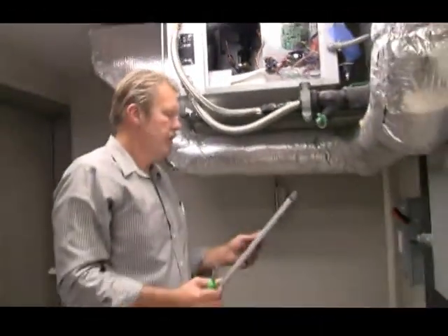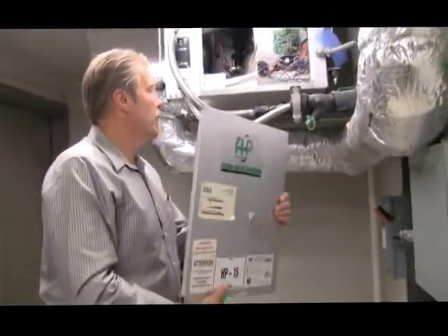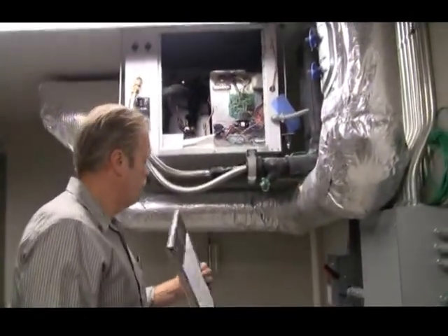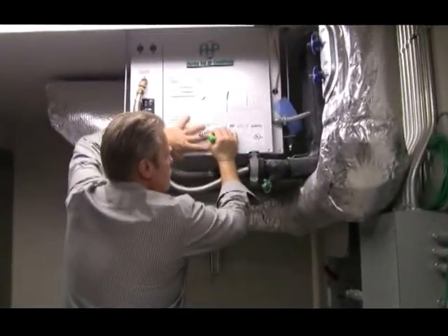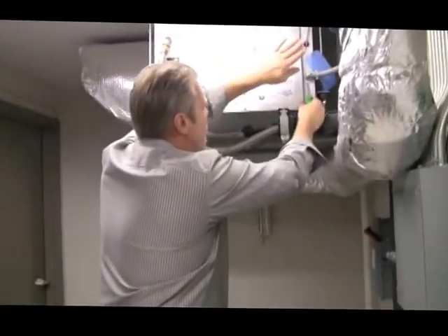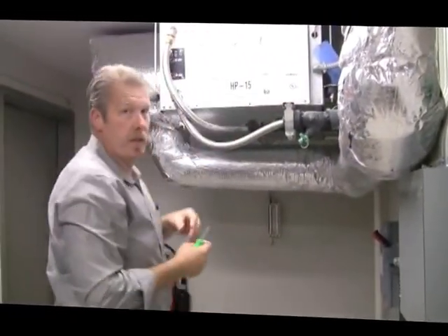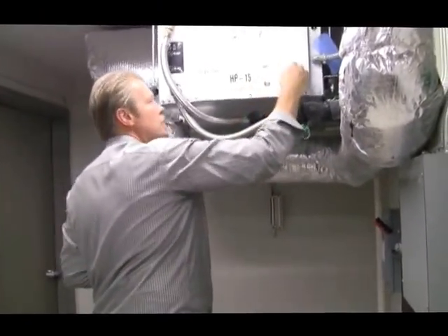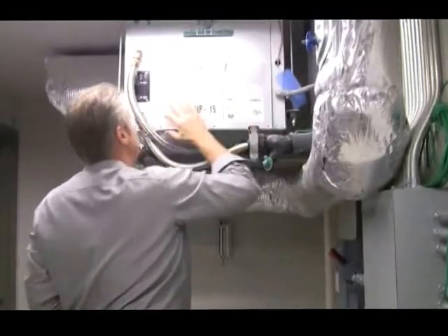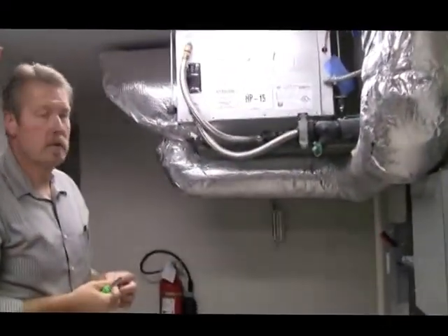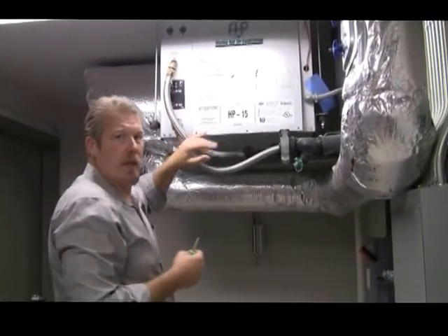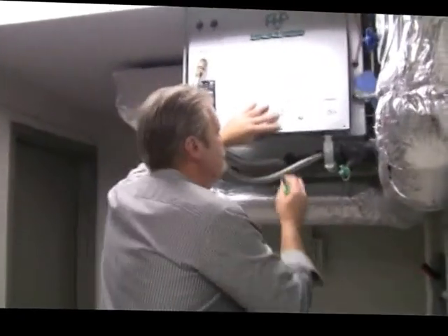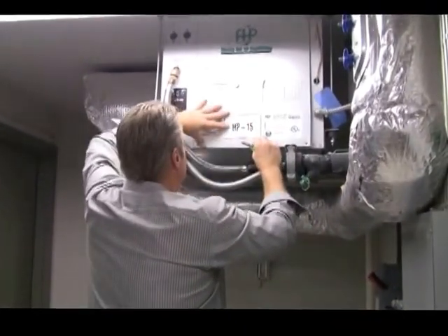It covers high pressure, low pressure, freeze sensor, and condensate fault. So if we have a blocked condensate drain, it'll tell us. If the compressor pressure is too high or too low, it'll fault out. A lot of times that information can help us troubleshoot the situation from off-site. So if you ever have a unit that's not running, you want to pull those 3 screws, open this cover up, and see what that light says, or what that light's doing, before you turn the power off. Okay? Just don't stick your hand in there.